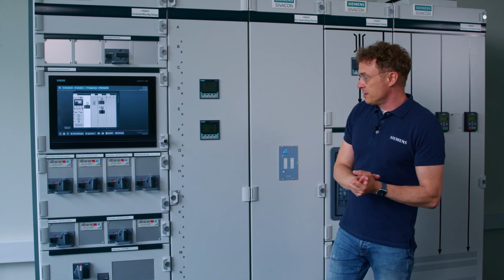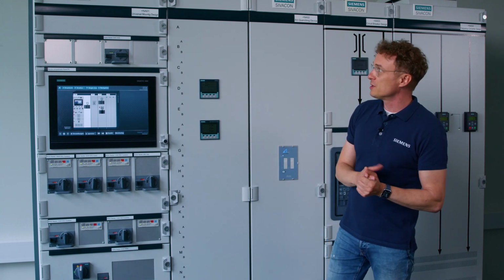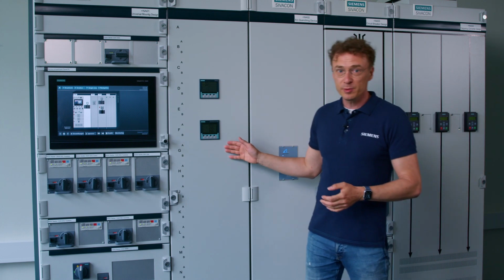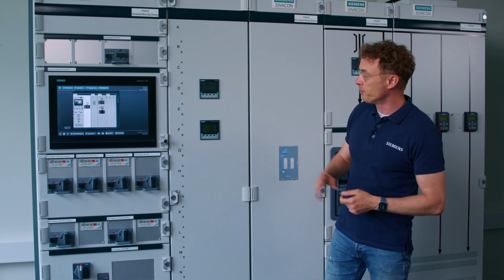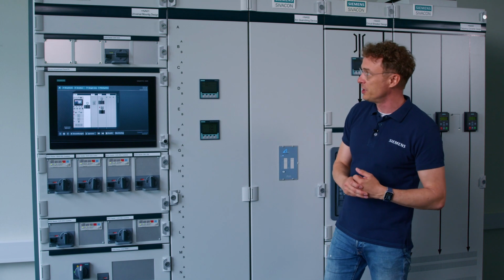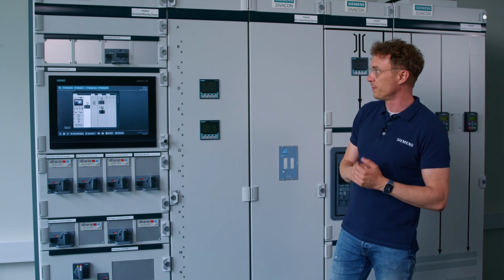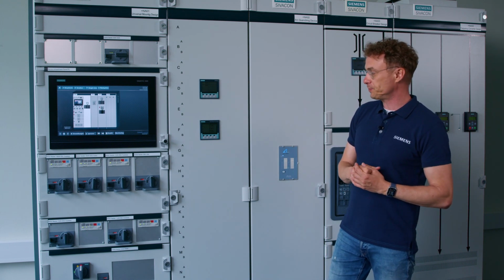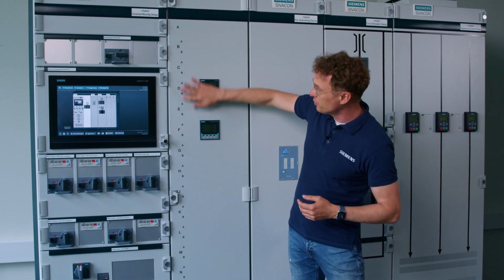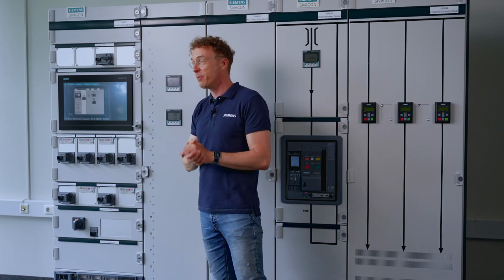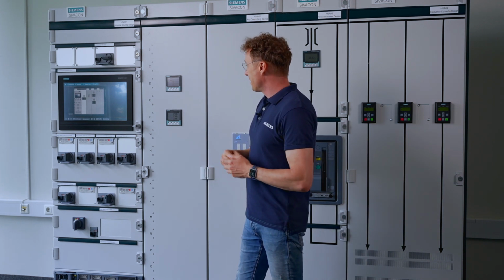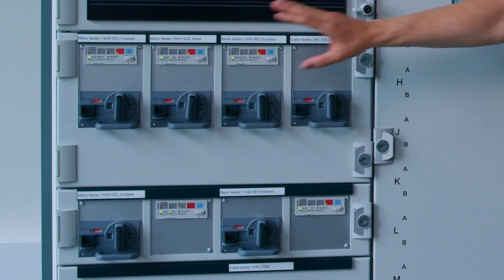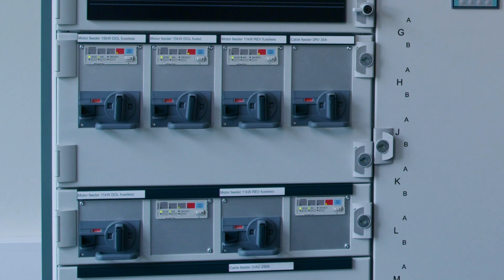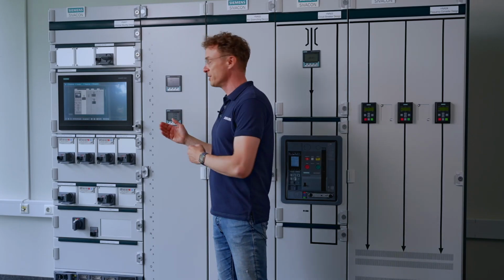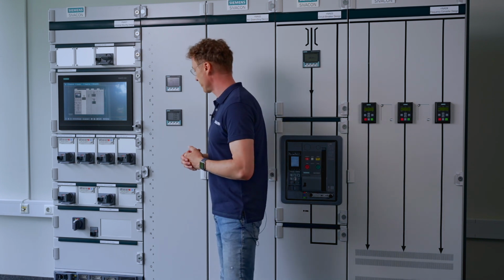The right door of the universal mounting design section is the cable compartment. Behind that are the cable terminations for power and control connections. And on the front of that door, we see this alphabetical grid. This helps you identifying the exact location of a feeder if you look it up in a circuit diagram and want to reference it to the switchboard.